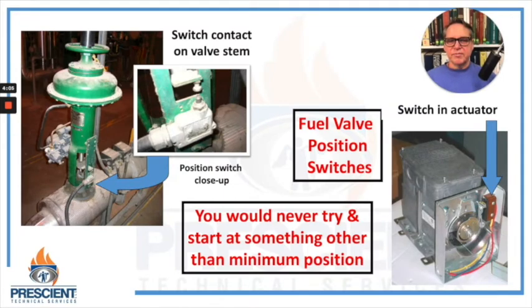So we talk about fuel valve position switches, and I just wanted to review with you the fact that just as you wouldn't go to the parking lot and floor the accelerator of your car and try to light off, you never want to light off a piece of equipment that's at anything other than low fire. So on relatively larger pieces of equipment, standards require that you have the gas valve at some minimum position. So sometimes that's done by a position switch or a limit switch associated with the fuel valve.